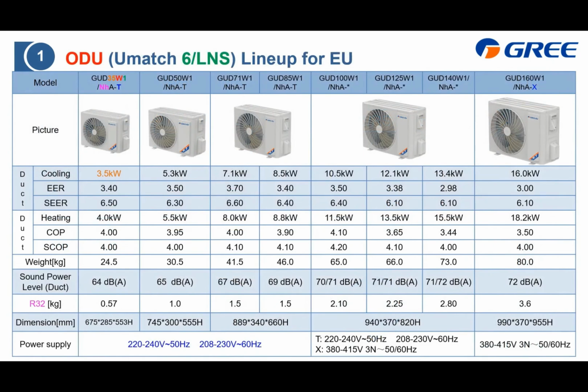This table displays the outdoor unit lineup for the EU market. Here is the model, and this is the picture. You can find that the whole series is a single outdoor fan design. In the model name, the number means the cooling capacity, here it is 3.5 kilowatt. This W means it is an outdoor unit. This one means it is our U-Match 6th generation, or U-Match LNS. This NH means the refrigerant, it is R32. The last letter also means the power supply. For this one, it means single phase. For this X, it is 3 phases.